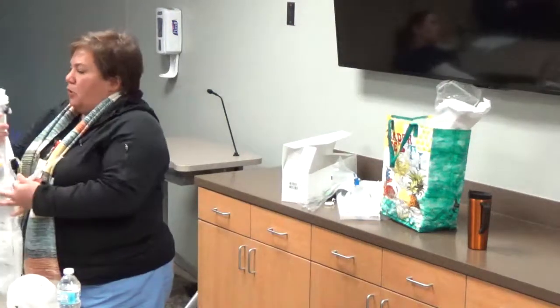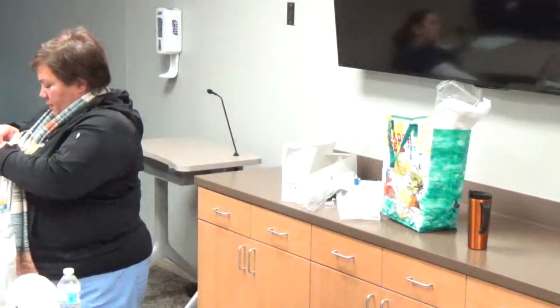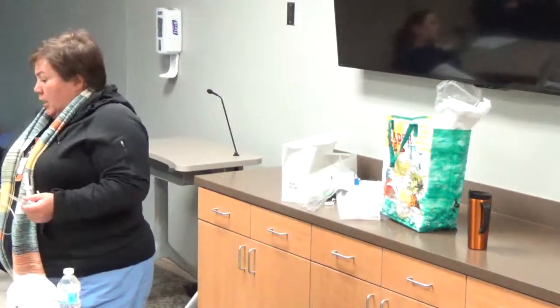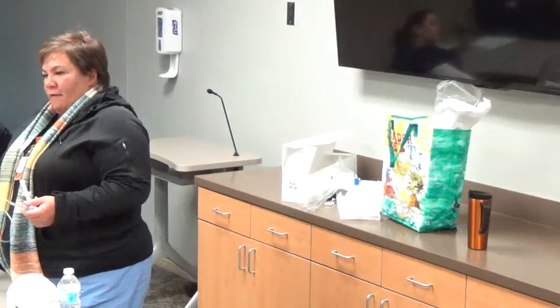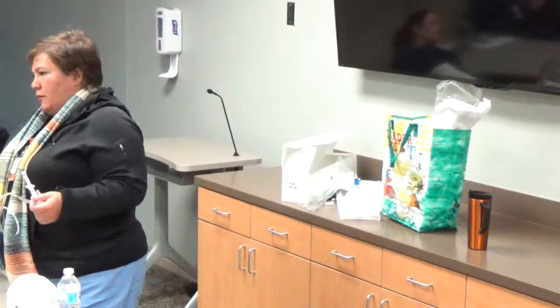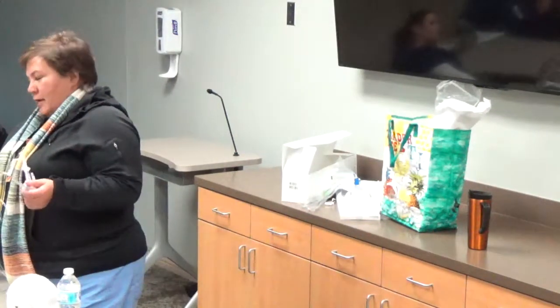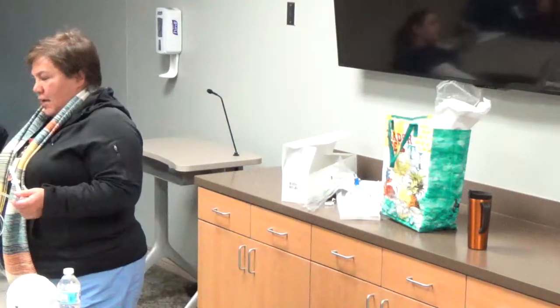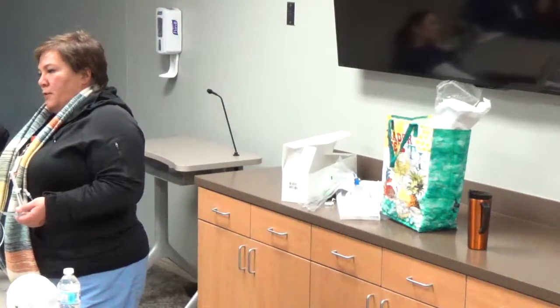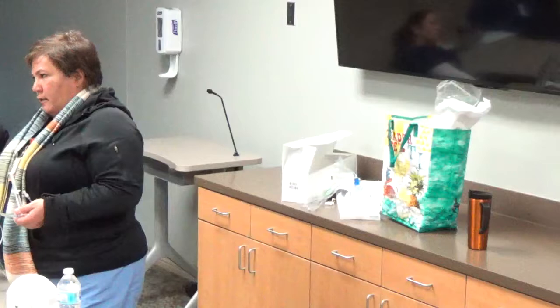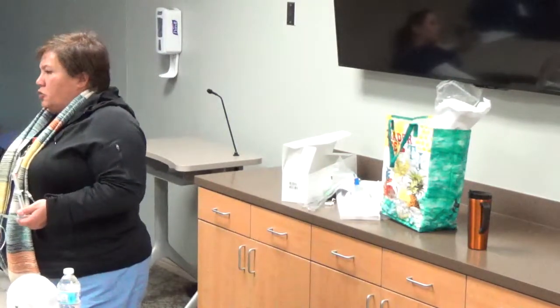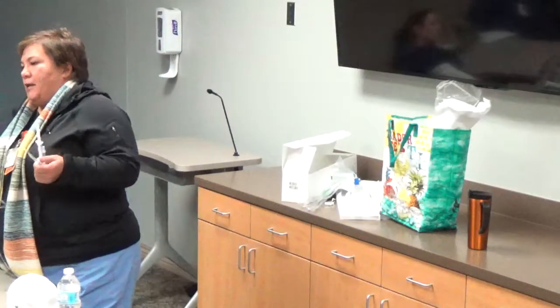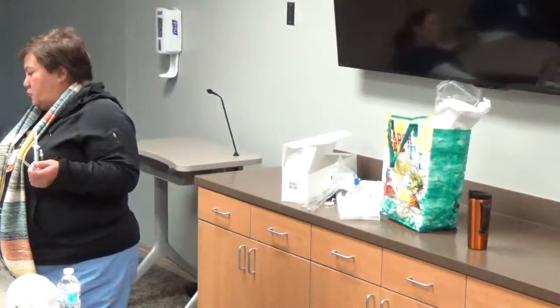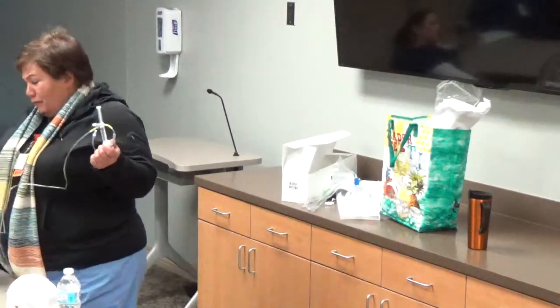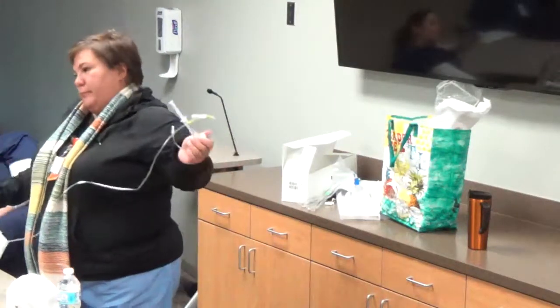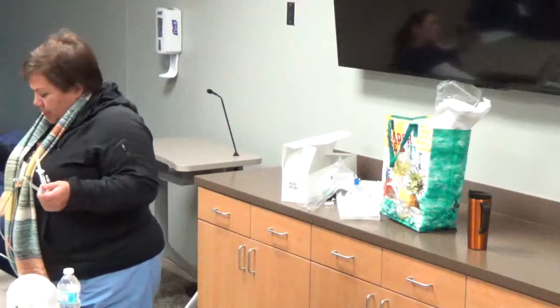This is the collection chamber. At the top of the collection chamber, you'll notice, I'll pass it around, there's an air filter at the top of the chamber. This can never get wet. If this gets wet, the entire system fails, okay? That is one of the things people don't realize, and I'm getting calls at 3 in the morning because my drain stopped working after a trip to CT, for example. It's usually because somebody put this down on the bed next to the patient, they never clamped off the drainage, and now my filter is wet. But how do you explain that to somebody who doesn't even know that there's a filter? It's kind of a problem.